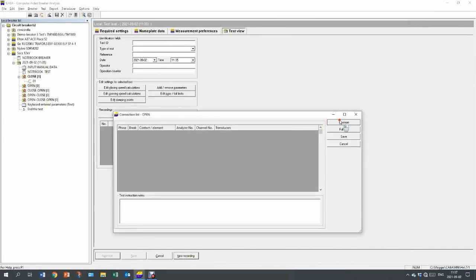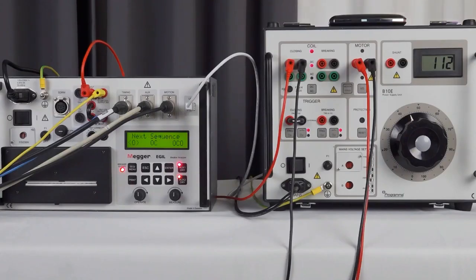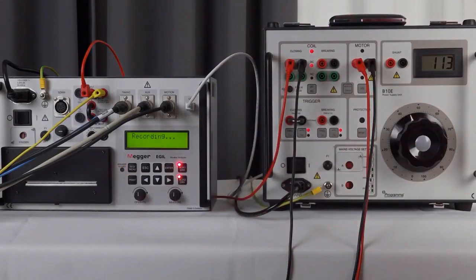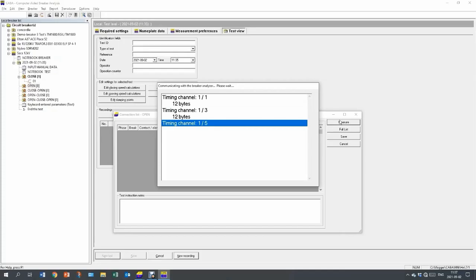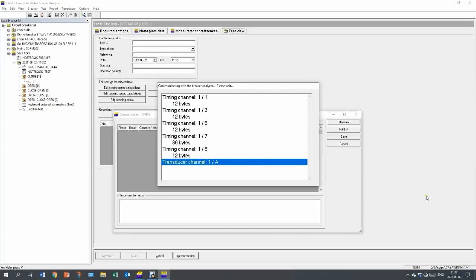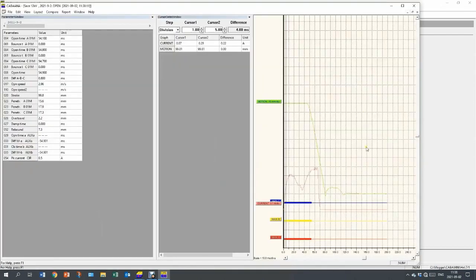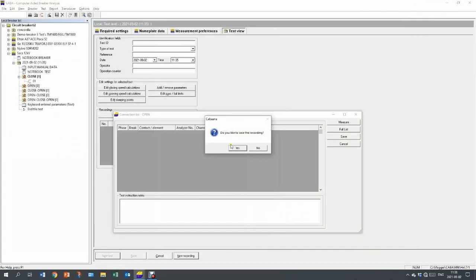New recording again, measure, and I need to turn the knob again. And there's going to be a bang. And again, here I get the timings. It opens about 45 milliseconds. And the red coil current and the green motion. I also can see here in the parameter list that I was saying wrong. It was actually about 54 milliseconds. It's easier to see it in the list format. And the maximum current was 0.5 amp. I close it and save it.